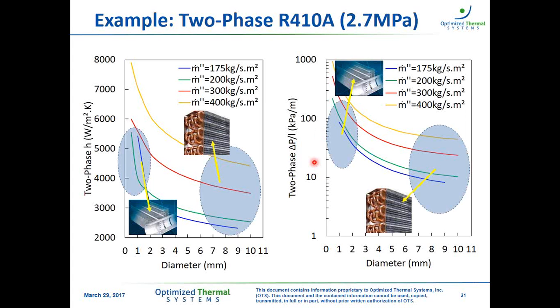Now, if we go back to the two concepts that we discussed in the previous slide, we have the microchannels operating all the way to this end of the spectrum with higher heat transfer coefficients, but also with higher pressure drop per unit length that is addressed by headers and multiple distribution. On the other end of the spectrum, we have large tube fin heat exchangers over here. If we move towards this direction, we're basically somewhere in between, because neither end of the spectrum is actually desired, and we can benefit from both if we have a tube fin heat exchanger concept that operates somewhere in between the two.